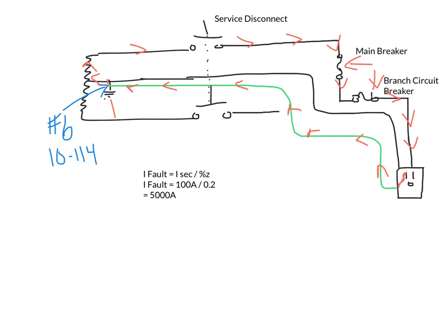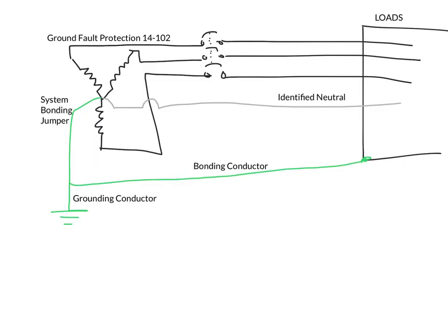The good news is that 5,000 amps of current flowing on the conductor should not happen for very long, because one of those fuses or circuit breakers in that circuit is going to open up to protect it. But keep in mind that fault current can be significantly higher than load current would be on any particular circuit.